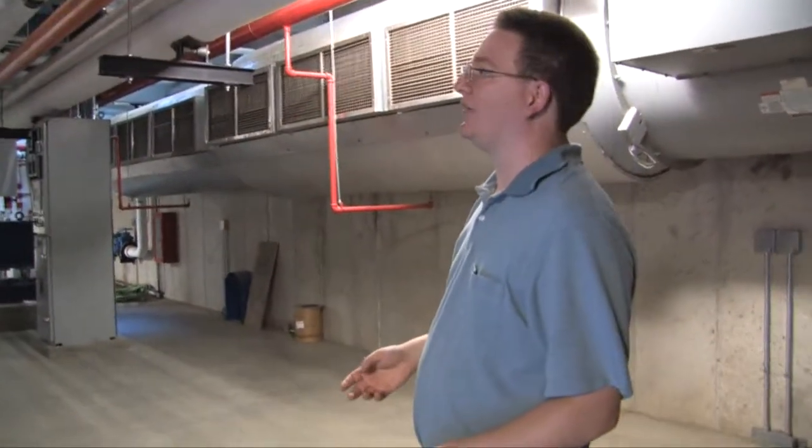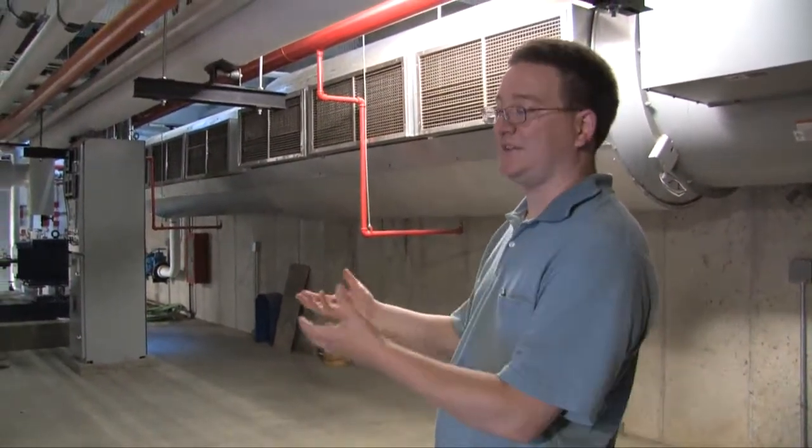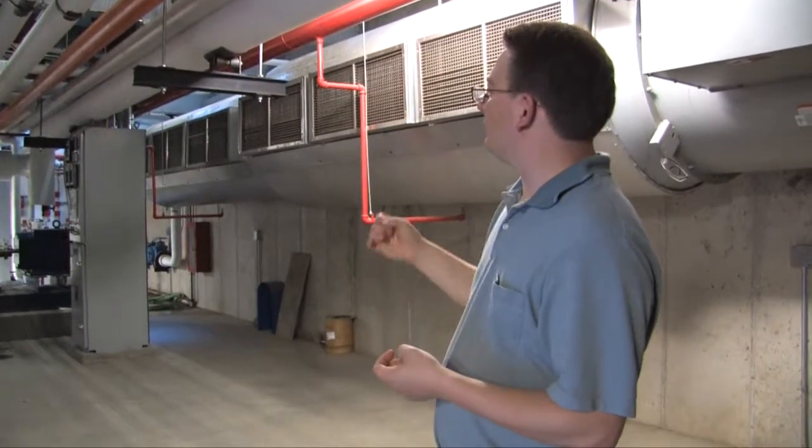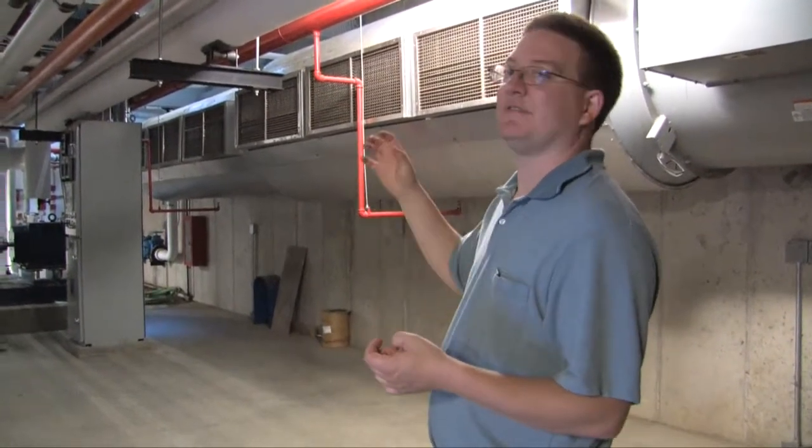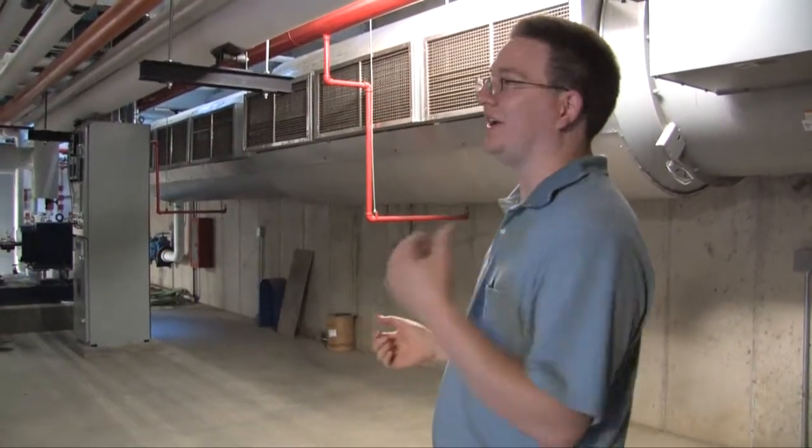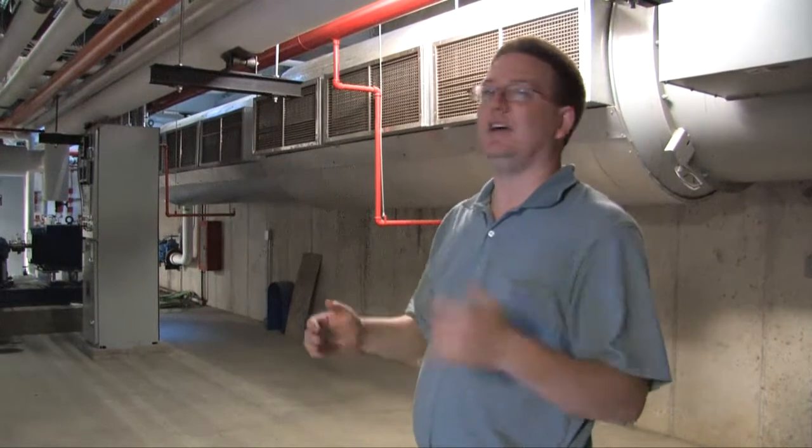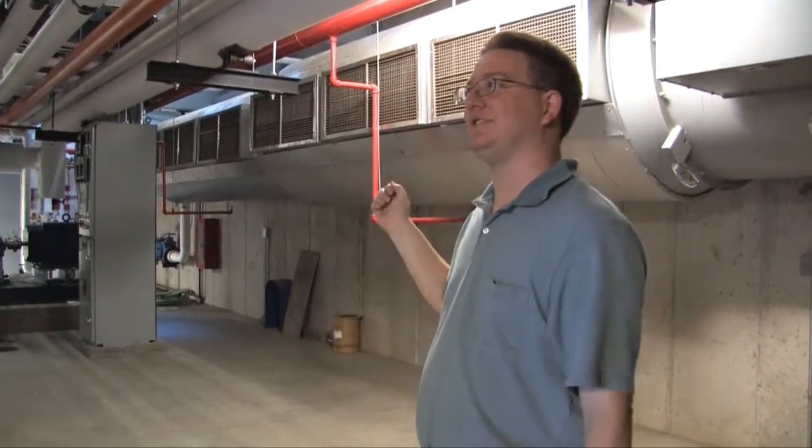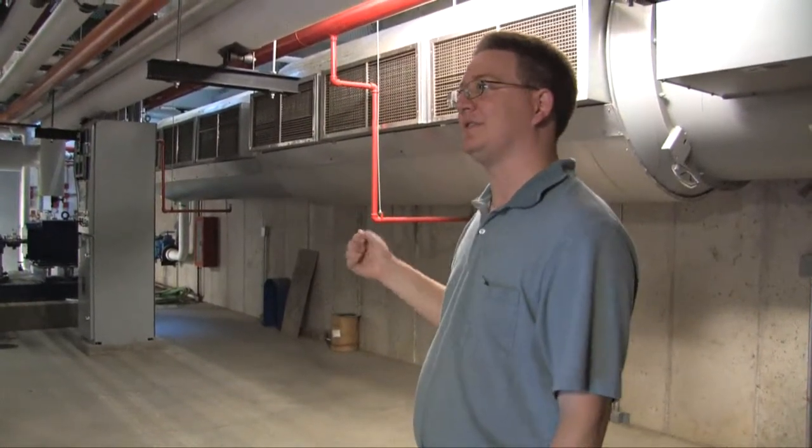That turbine will take our boiler steam and generate electricity with it. What we have here is that we have a boiler that will generate 280 pounds per square inch, and then it goes out to campus at 15 pounds. And we use that difference in energy to generate about 320 kilowatts of electricity.